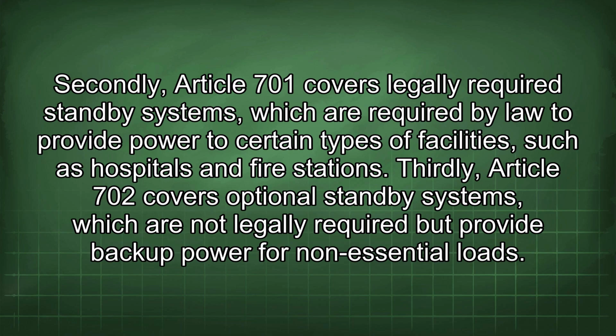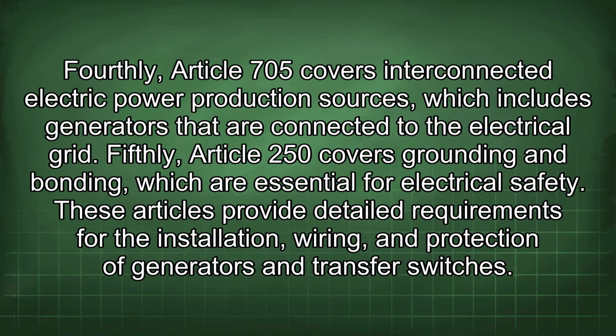Secondly, Article 701 covers legally required standby systems, which are required by law to provide power to certain types of facilities, such as hospitals and fire stations. Thirdly, Article 702 covers optional standby systems, which are not legally required but provide backup power for non-essential loads. Fourthly, Article 705 covers interconnected electric power production sources, which includes generators that are connected to the electrical grid. Fifthly, Article 250 covers grounding and bonding, which are essential for electrical safety.